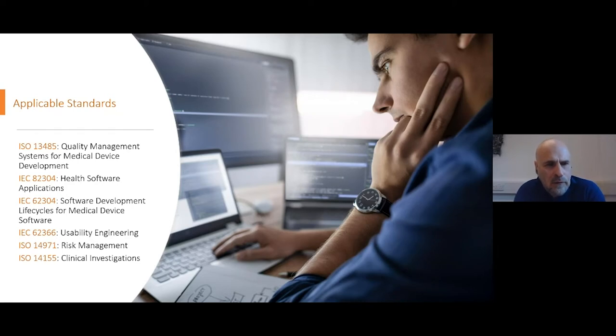This is a high level standard for software only and software as a medical device applications that would cover AI and ML. What it defines are some of the requirements such as labeling for software specific devices that don't actually have any packaging. So how do you display the label and meet the labeling requirements that's in the regulation? It's one example of what is covered in IEC 82304, along with validation of software.